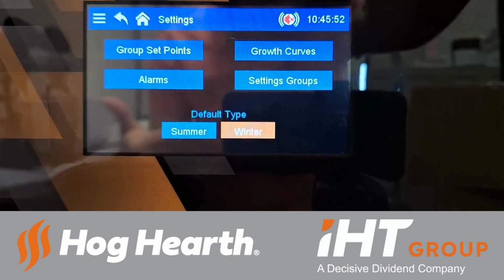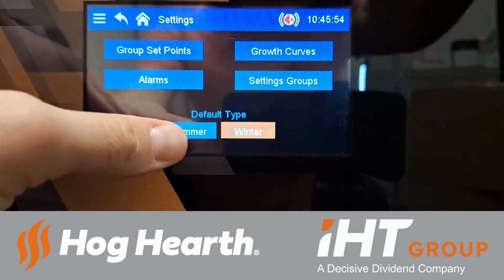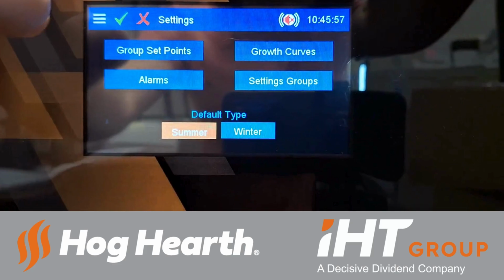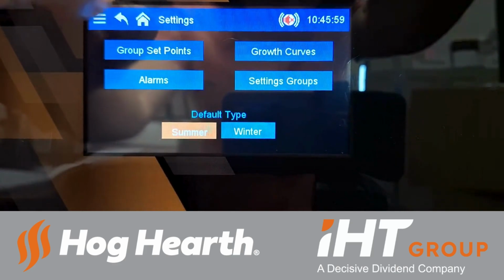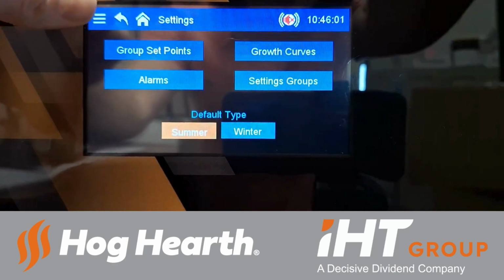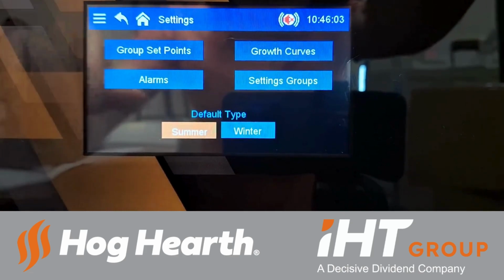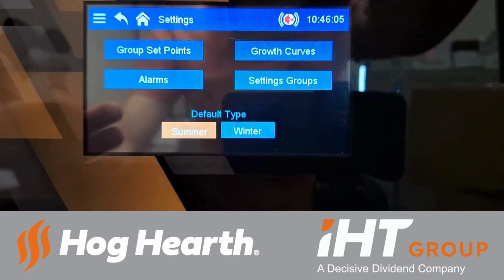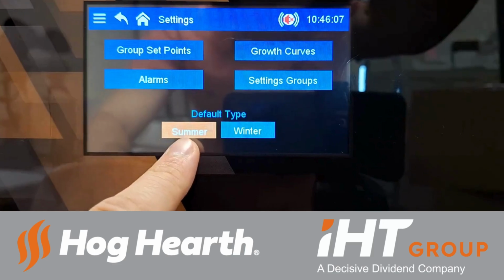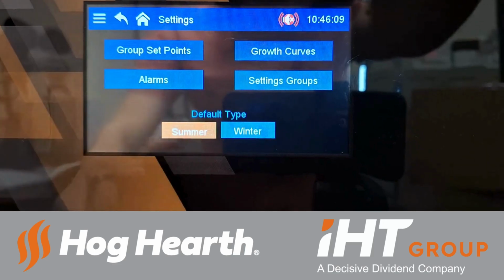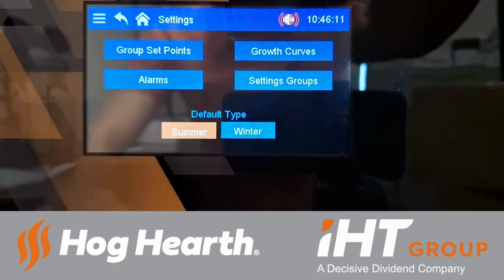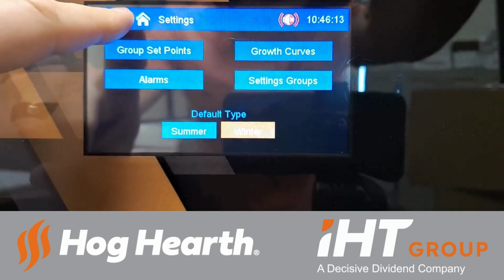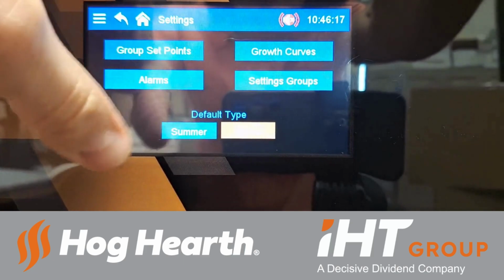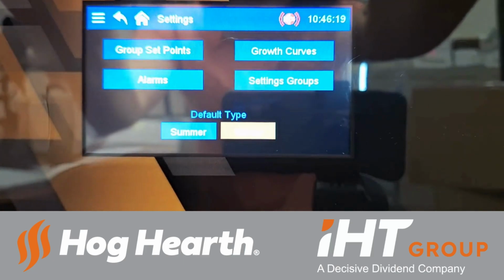If you wanted the summer growth curve, you would need to go to summer, you would need to save, and then you'd need to go into the menu, go into administration, and you'd need to restore the defaults. And then you would have the summer growth curve as the default growth curve. Just changing this selection here won't change it. You need to then restore defaults. So for now, the default is winter. It is going to be winter, so I'm going to show that.